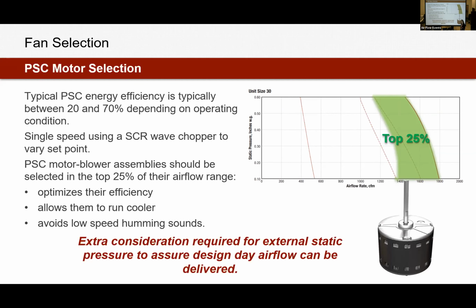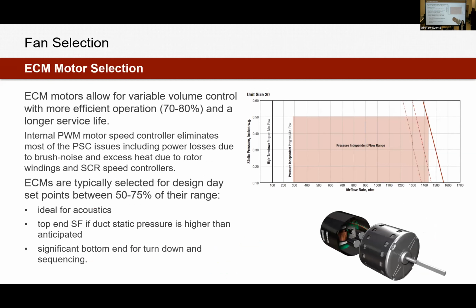Don't use PSCs. Instead, use ECMs. Your efficiency is much higher, always in the 70–80% range. So you're staying at a higher efficiency through the entire range of the motor. And it's got a longer life with a much higher turn down. So for example, here you can see we can turn down from 1400 CFM all the way down to 100 CFM. You have the variability wired up to your BAS system and remotely change the speed. That's not the case with PSC. It's a set it and forget it.